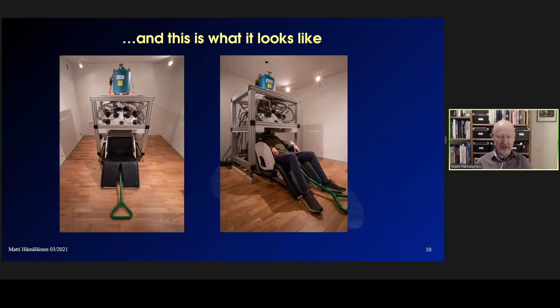The third device we have built is a combined stimulation and acquisition system. It combines transcranial magnetic stimulation and MEG, and it has 16 liquid nitrogen cooled TMS probes, which can be used to stimulate different parts of the brain selectively. And then it has 25 optically pumped magnetometers for recording the MEG. The arrangement is schematically shown here on the lower right, but this is the actual device in the laboratory after it was assembled together. And on the right we have a subject sitting in a chair under this helmet, which has the TMS coils, 16 of them, and MEG recording sensors.